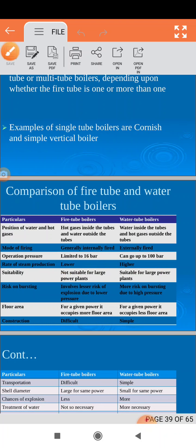The next comparison is the rate of steam production. In a water tube boiler, water is in the tubes and fire surrounds them, so heat transfer is greater and higher temperature steam is generated more quickly. In a fire tube boiler, fire is limited inside the tubes, so water does not receive as much heat, resulting in a lower rate of steam production. Therefore, the rate of steam production is higher in water tube boilers.